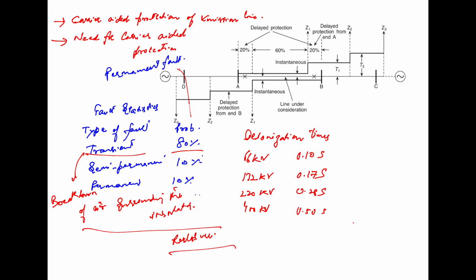Now, some of the typical deionization times for various system voltages are given here. For 66 kV we will have 0.1 second, then for 132 kV we will have 0.17 seconds, for 220 kV we will have 0.28 seconds, and for 400 kV we will have 0.50 seconds.